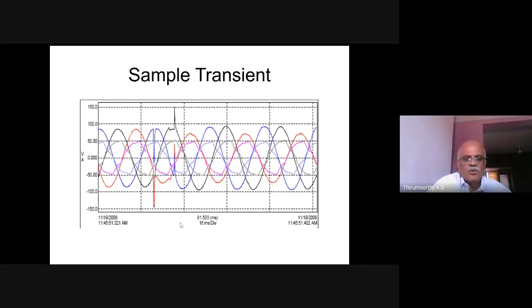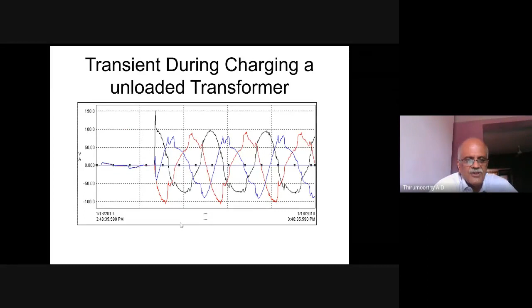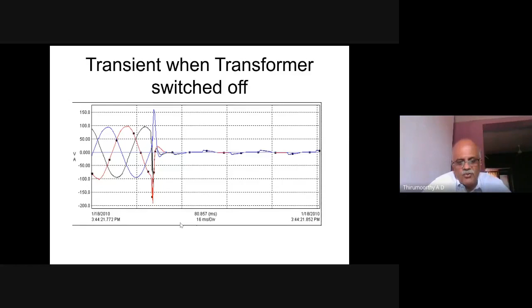So this is a transient. You can see each and every time you switch on and switch off the transformer, there is a transient. The transient may travel up to the end consumer. This was recorded in the customer facility when the transformer was switched on and off. Whenever the transformer is switched off, the quantum of transient is more than the quantum of transient occurring during switching on. This transient is during switching on, and this transient is during switching the transformer off. You can see the quantum of transients occurring. It is dangerous to the equipment, and at one time the installations and equipment will fail.